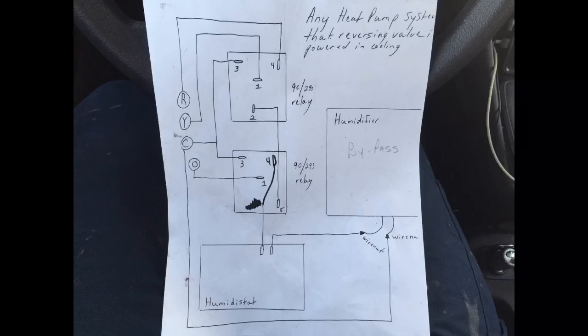Typically I don't care to do my relays running off of system transformer power. Now, if you are going to add very much to the system, you'd be better off adding a transformer or upgrading the transformer in the system to a larger transformer to handle the additional load of all of those 24 volt coils. So for this diagram, let's just walk through what we've got here.